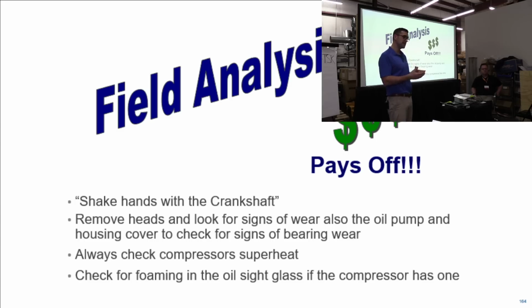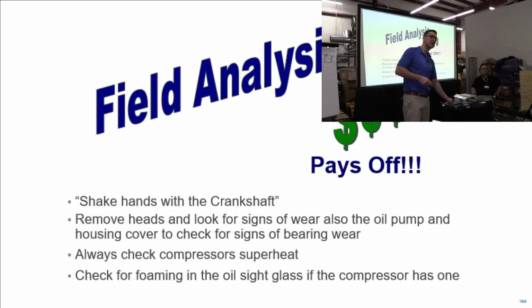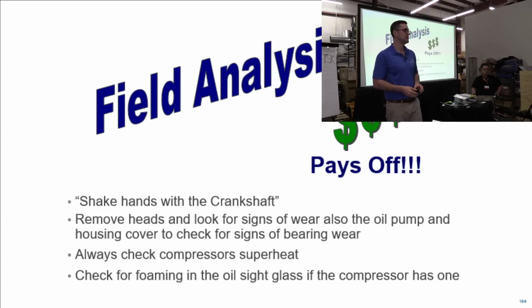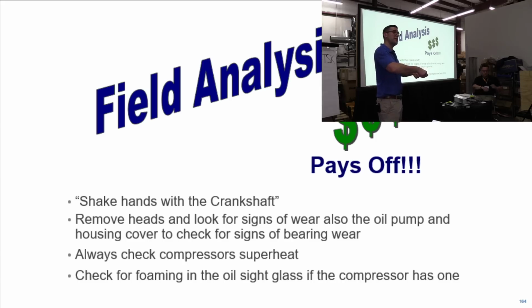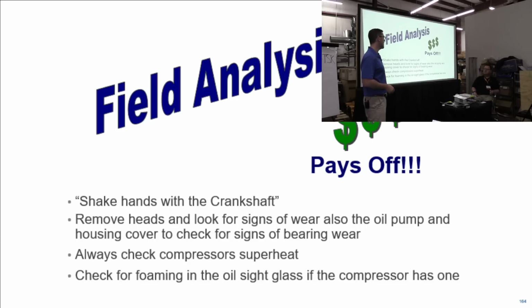Look at the pump gasket. Look at the pump bearing. And then one thing to do is shake hands with the crankshaft. If you got up and down play, what does that mean for that bearing? Yeah, it's worn. And now that's why you're checking it and you got an electrical failure. That rotor probably drug on the bottom and you have a stator fail. Okay, always check compressor superheat. Look for signs of wear. Right? Take it apart. Take a look at it.